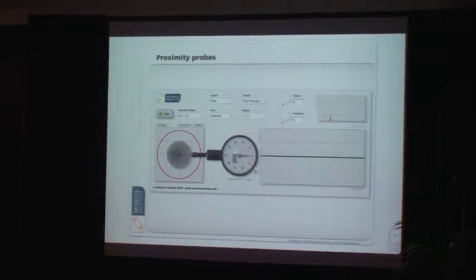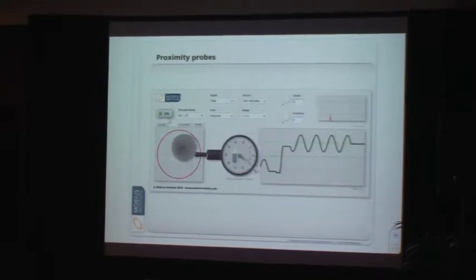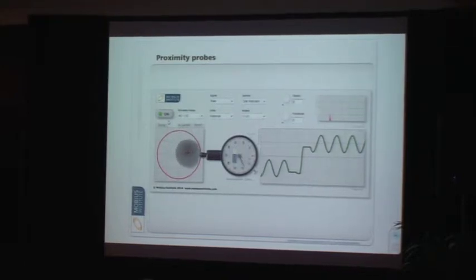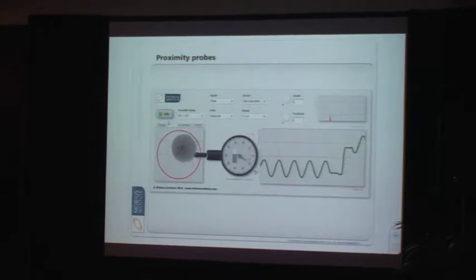Just to keep it simple, we're using a dial indicator instead of a proximity probe. As this shaft turns, exaggerating the motion, we see the nice little sine wave we're all familiar with. But if I push the shaft over this side of the bearing and spin it, we might have a rub here, and you can see the sine wave is still there, but offset. If I drag it back closer, we still get a sine wave because the actual movement is the same, but now that it's closer to the probe, we get this offset.